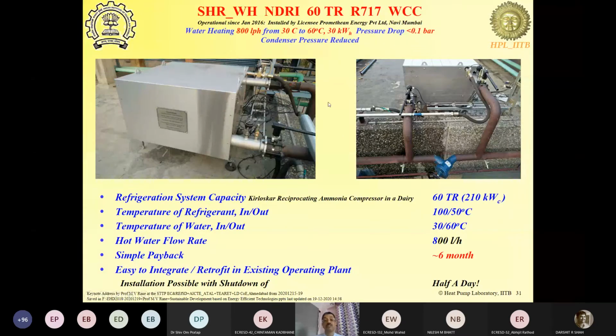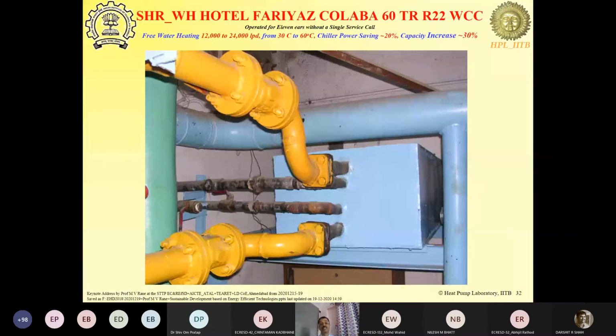These are some examples of installations in NDRI dairy by one of my licensees where the payback period was less than 6 months. Water heated from 30 to 60. Refrigerant was being condensed, cooled from 100 to 50 degrees centigrade on a 60-ton chiller. So this unit got integrated in less than half a day. Okay, so no significant downtime is required for that. And the heat exchanger on the ammonia side was carbon steel and stainless steel on the water side. This was at the Hotel Fariyaz, as I told you.